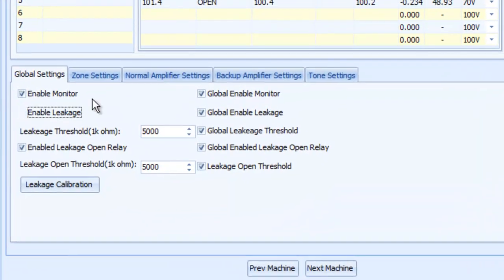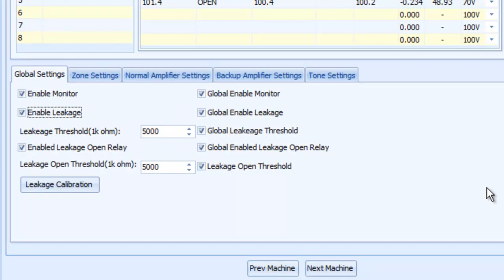I do want to enable leakage, which is if it detects any leakage between the IDA8's output, which goes to the balanced input of the amplifier, and then the amplified output back to the circuit, it unloaded and loaded, it will see that. So if there's anything broke or anything's grounded, that will give you an indication that there's a problem between the IDA8 and the amplifier. Anything that says line A or B monitor issues, like whether it's a short or open, it'll give you a line A or B fault, and that is the actual speaker line having a problem.